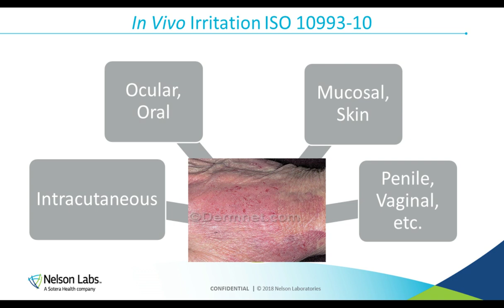So we start here with sample preparation, which is outlined for us in ISO 10993 Part 12. We can see here that we can test either raw materials if we need to for screening purposes, which we have here in a test tube, or in the middle of the screen, we just had this nested cube. So we really like to test final finished devices in vivo and in the in vitro assay as well. What we do is we cut up the device if we can, and we put it in an extraction container. And then we extract it in a polar and a nonpolar solvent. So our polar solvent is typically saline, and nonpolar solvent is an oil, either sesame oil or cottonseed oil.